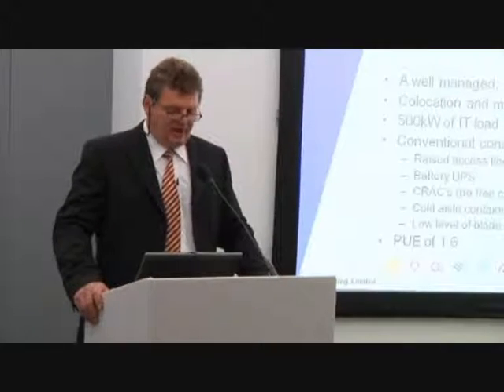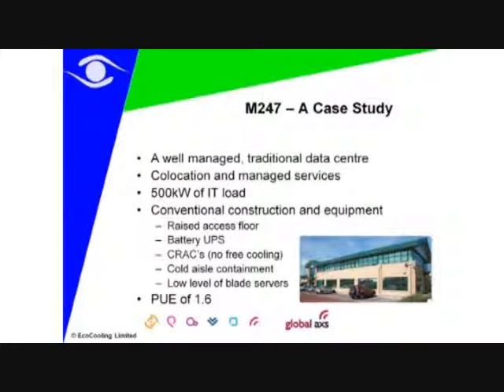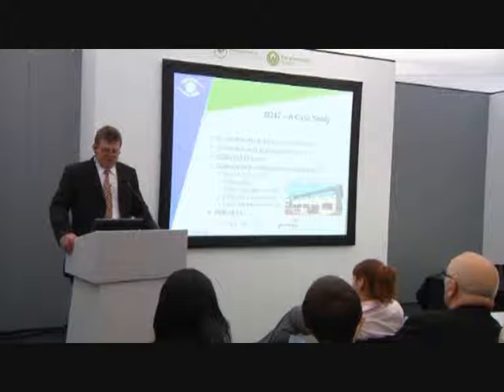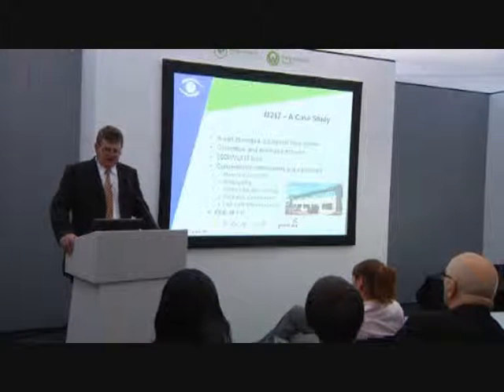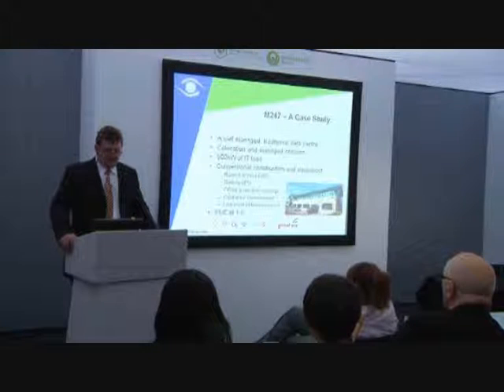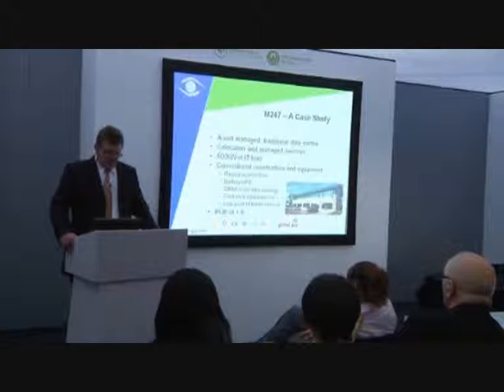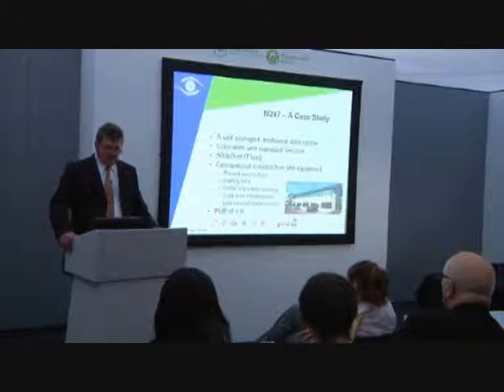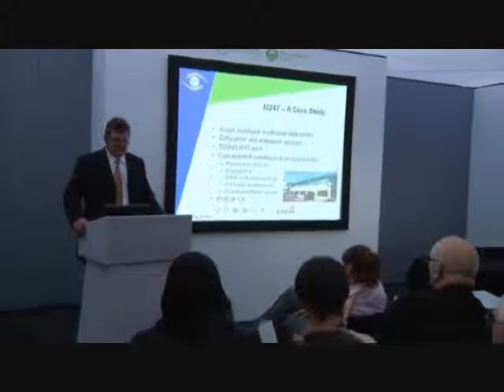The company I'm going to talk about is a company called M247 up in Manchester. The reason I'm going to talk about M247 is it's a very professional, well-organised, traditional data centre with conventional equipment. And they were looking for a retrofit solution with nothing too complicated or too bespoke. They've got their 500 kilowatts of load, a conventional raised access platform floor, conventional CRACs, conventional racks. And they're running at a very good level of efficiency for that type of data center.